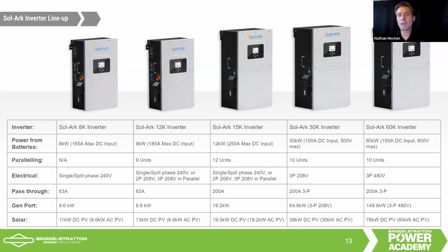The two inverters on the right side of the screen have battery offerings for high voltage projects. 208 volt would be the 30K inverter, and 480 3-phase would be the 60K inverter. Those are Y configuration inverters—you can't do delta with them, but you could with a transformer.